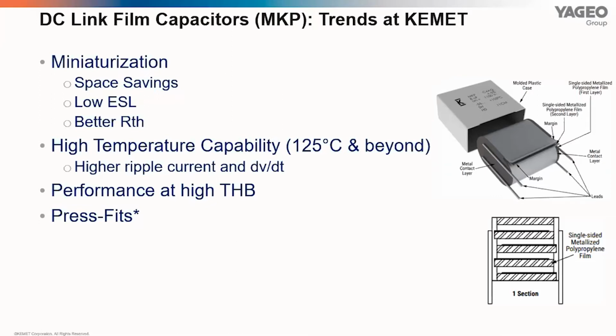Our R&D recognizes that the physical size of film capacitors and high temperature performance, along with long lifetime at those temperatures, is a crucial bottleneck in designs using film DC link capacitors. So they're constantly working on miniaturization and increasing the maximum operating range of these capacitors, due to which we presently offer temperature capabilities up to 125 degrees Celsius in a miniaturized box version, which we expect to increase even further in the future.